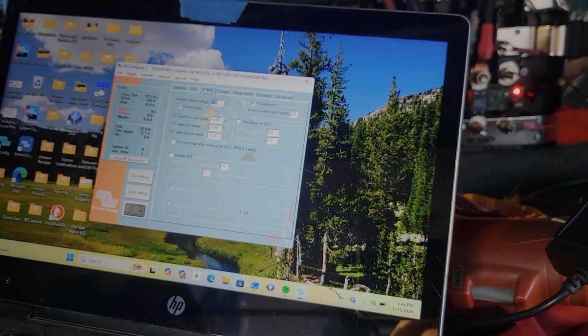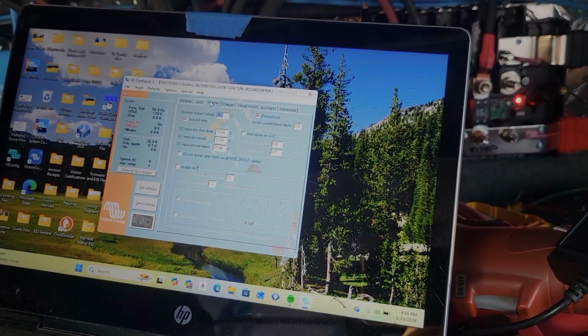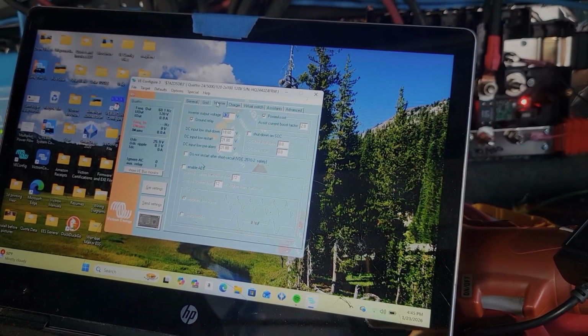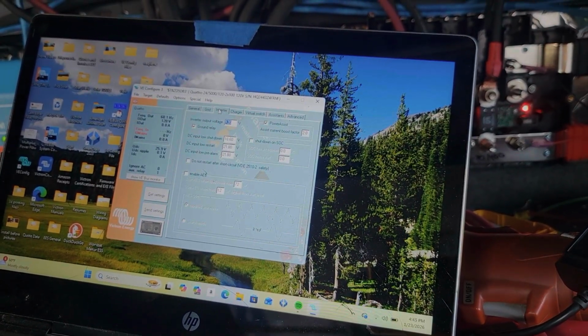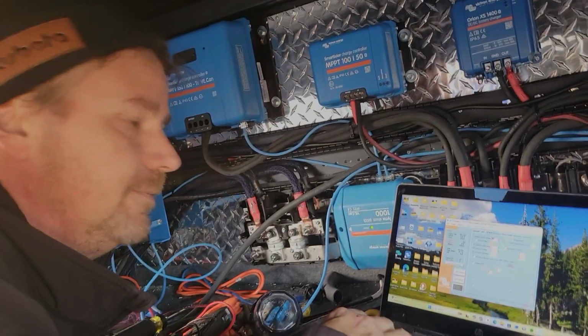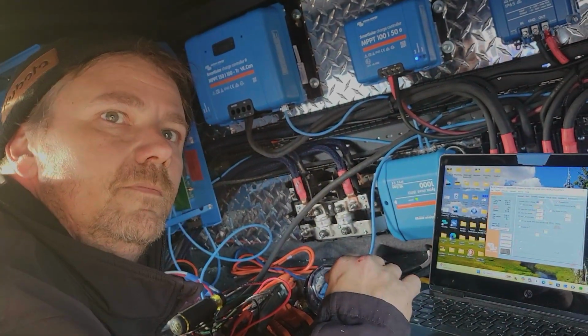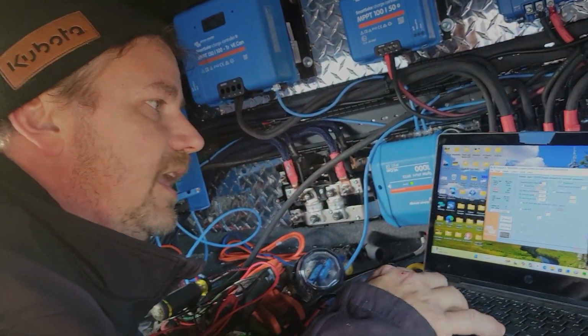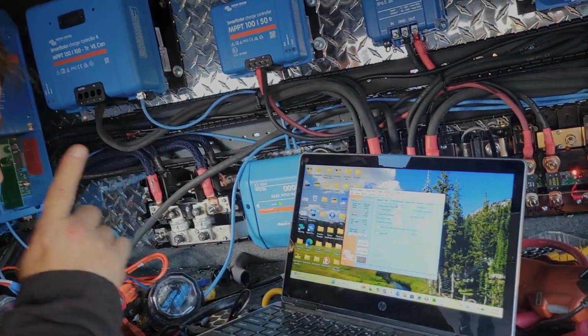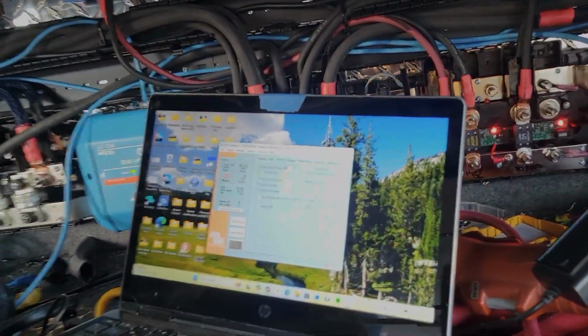If I disabled that, it would take like 20 or 30 milliseconds to switch over, which is still as fast as the blink of an eye, but it's not UPS quality. Well, and the difference is that my computer might see it and shut off. Correct. All right, so the next thing, on mobile systems, we want a ground relay enabled.